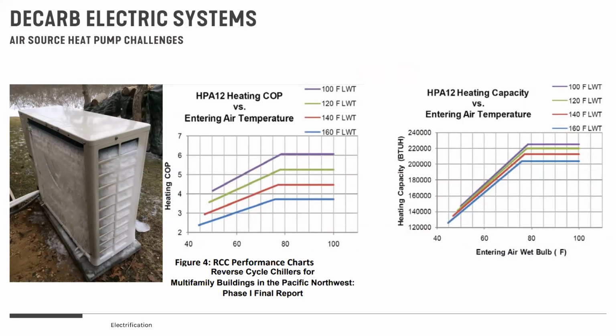Hot water systems or heat pumps have one area where they're weaker than a gas-fired boiler. Because they're trying to steal heat from the air, they struggle when the air gets cold. You can see on these graphs the efficiency of the unit as outside air drops; as the air goes down toward 40 degrees, the efficiency of many of these units drops to 3 or maybe even lower. We have to size a system large enough to account for that lower energy production. The other downside is that as it gets colder, the amount of heat they can actually make also drops. So it's really important when sizing these systems to look at climate data.